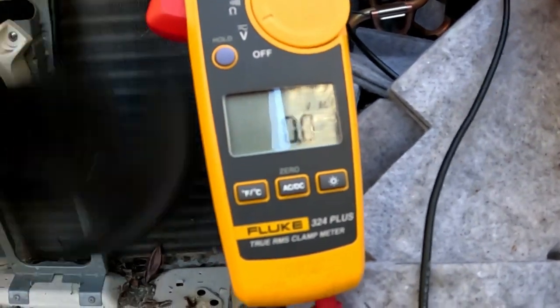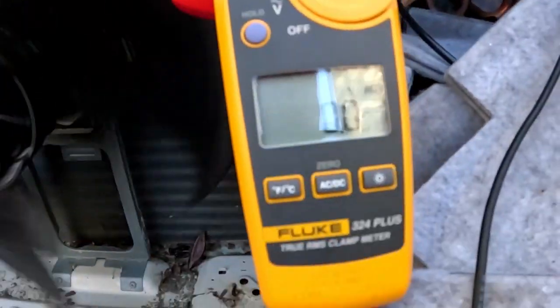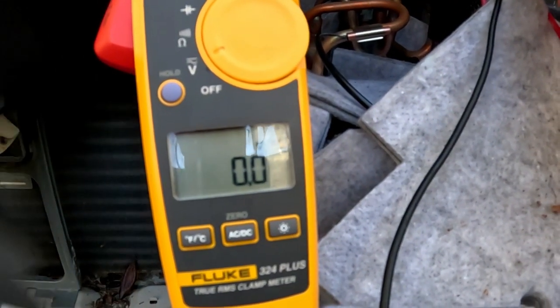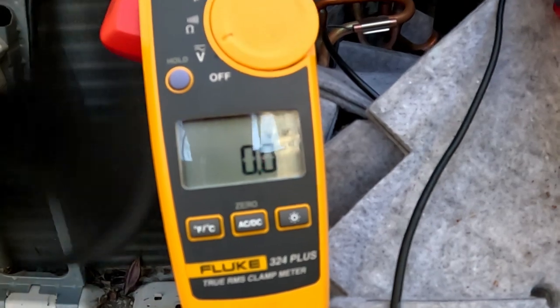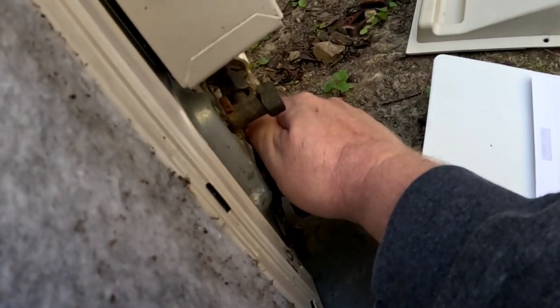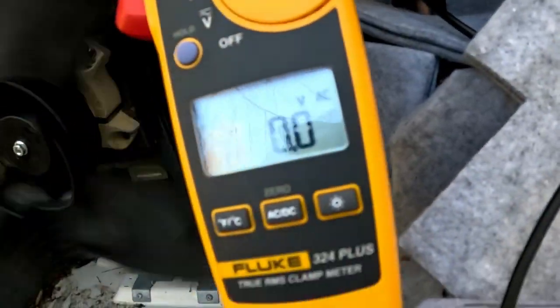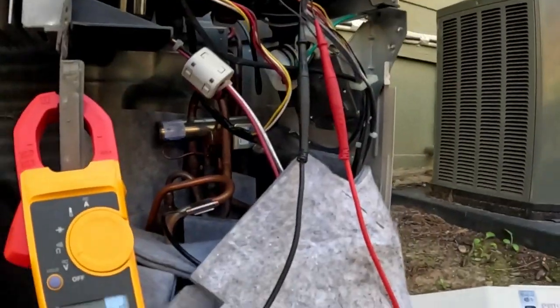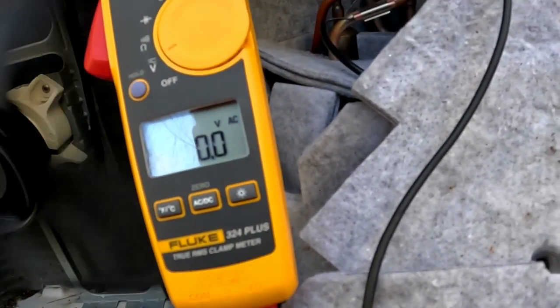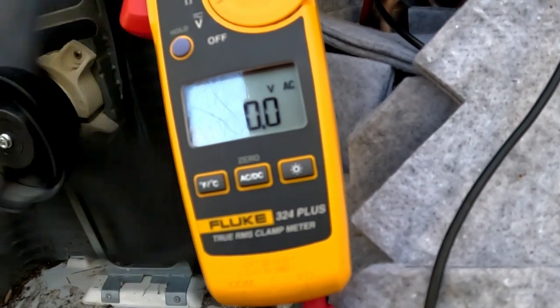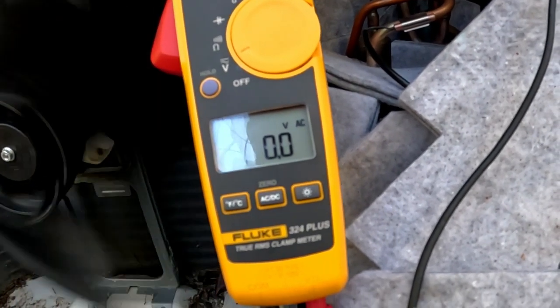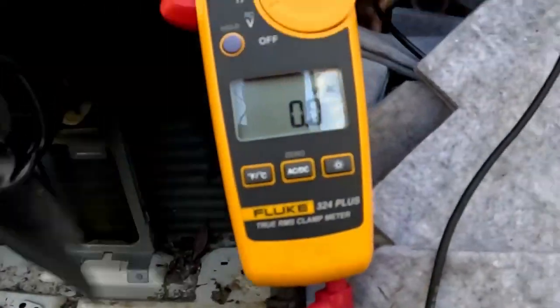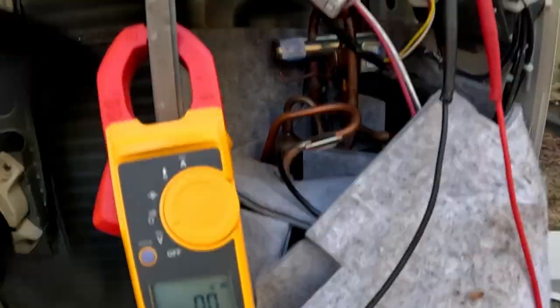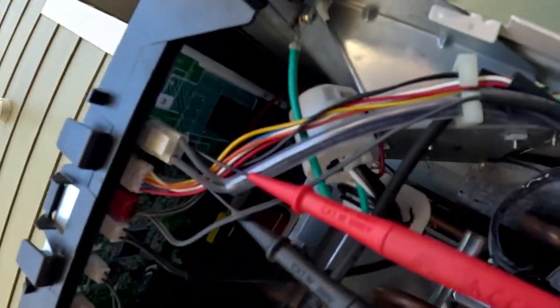That suction line, as you can see, we never got any voltage. Those things are in there snug. Right there. We never got any voltage, so I'm going to go with the fact that line's getting colder. So it's stuck in cooling. At some point that coil temperature sensor up there on the air handler doesn't sense the heat exchanger coil warming in heat mode. It's going to shut this thing down, and it's going to flash that E99 fault again. It tells you got a problem with one of these things in this reversing valve. Fujitsu, guys, you gotta love it.